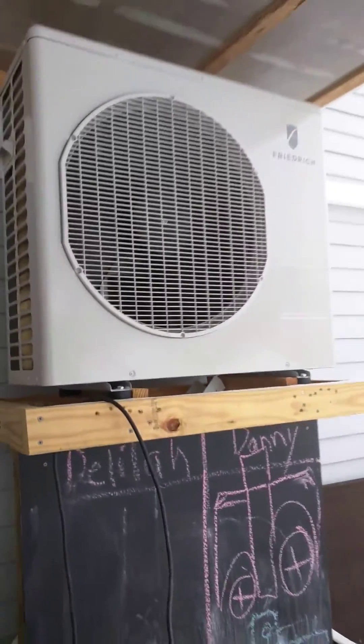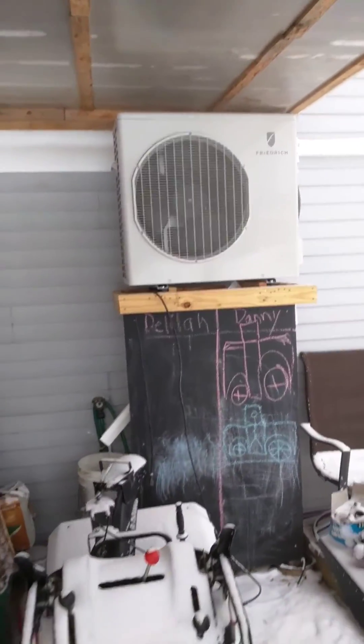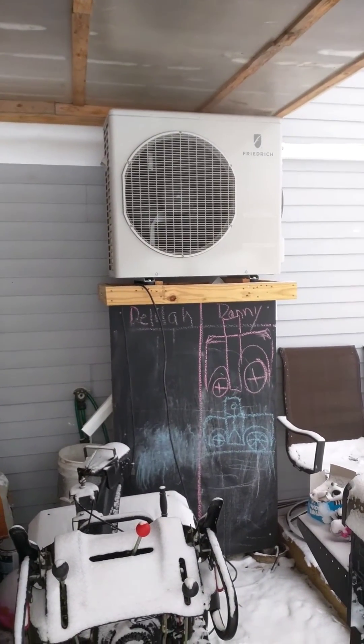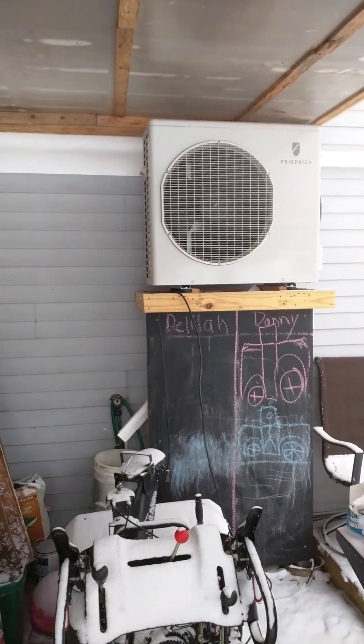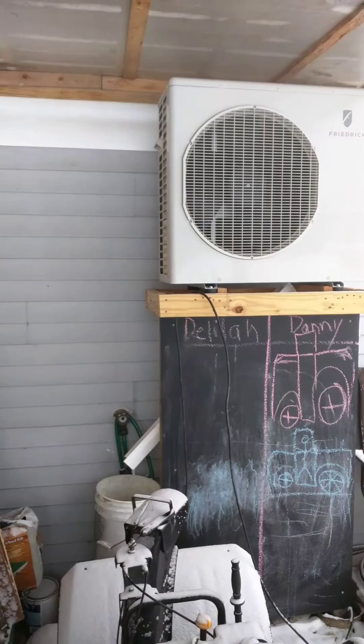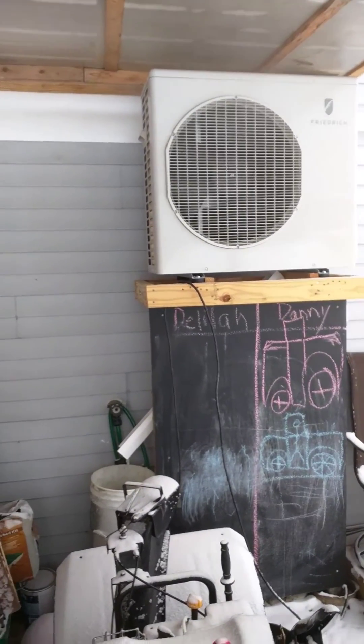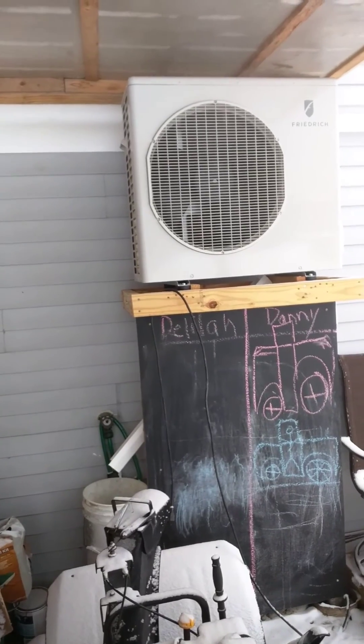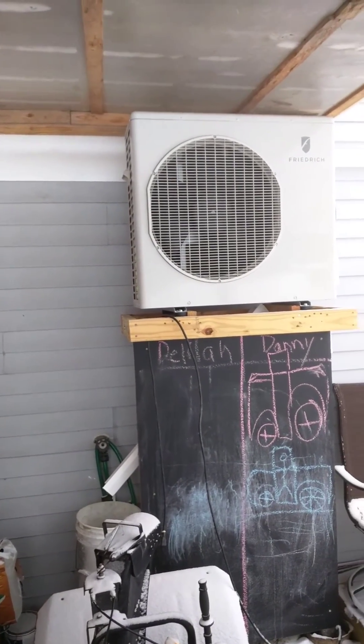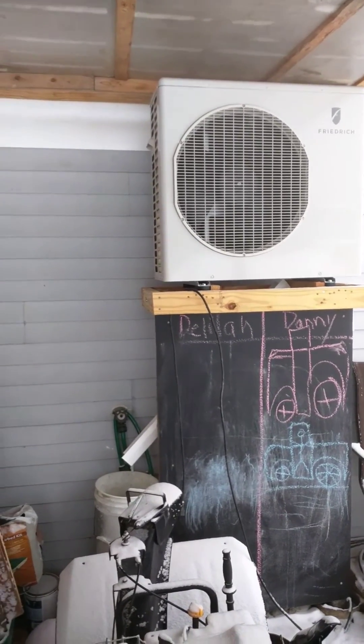The unit is mounted outside underneath a high deck, away from the elements — rain and snow. It seems to work pretty well. It's currently 2 degrees outside right now. It's pulling 2200 watts, keeping my house at 74 degrees. And an upstairs unit is probably pulling right around 800 watts, bumping the temperature up to about 72 degrees from 60.